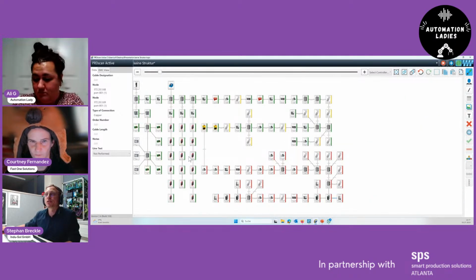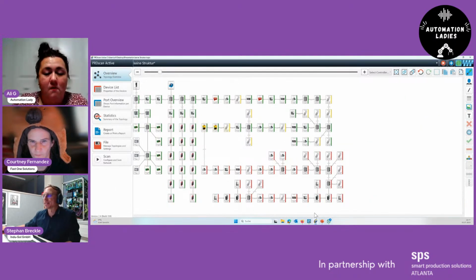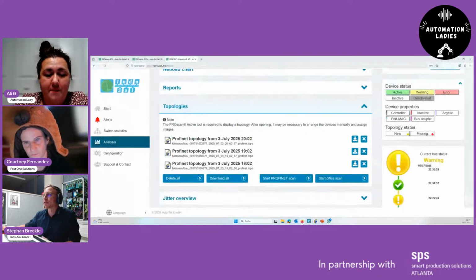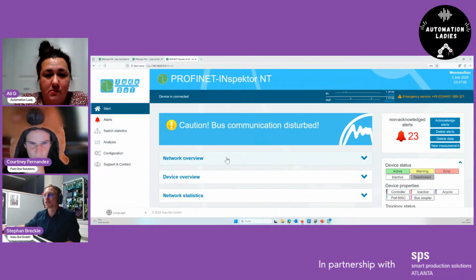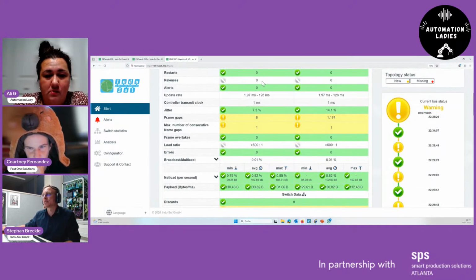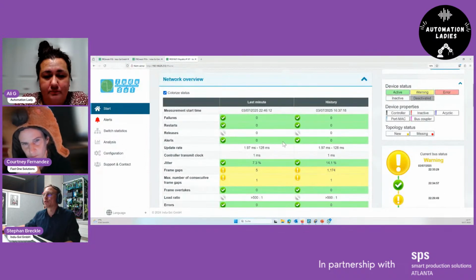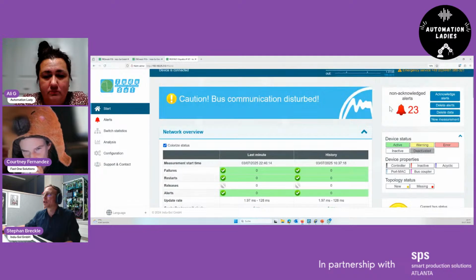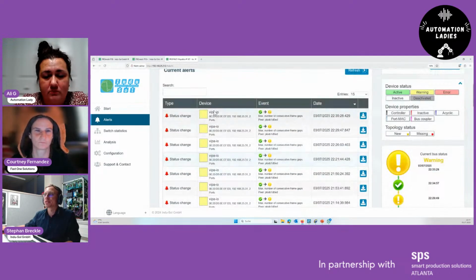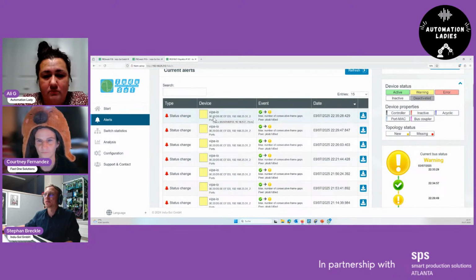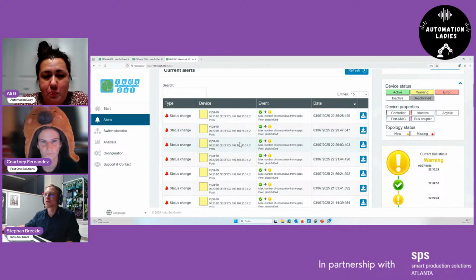This is how you can do analyzing and troubleshooting very simply with our solution. Normally you just connect the device and get the information. If you have an Ethernet or PROFINET issue, or just a simple device issue, all issues are written here in this alert list, where you see what kind of device, what the issue is, and the date. If you want to do deep analysis, you also get a Wireshark snapshot where you can do real frame analyzing.